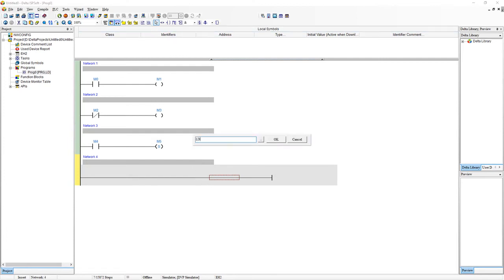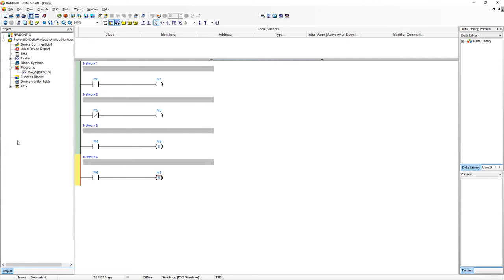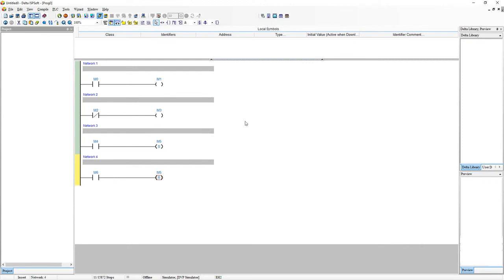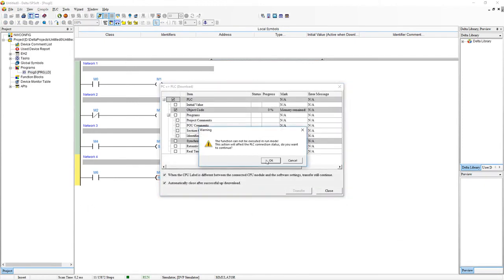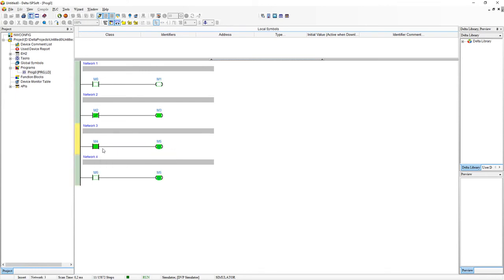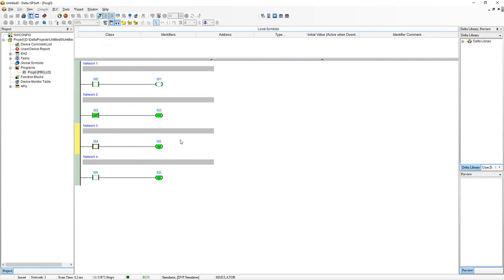So let's do LD M6. And we'll add RST as our function M5. So RST basically stands for reset. And I think it's quite obvious what this is going to do. But let's go into online mode and just demonstrate what it does. Alright great. So let's turn M4 on. So M5 is on. Turn it off. And M5 remains on. Let's turn M6 on. And you'll see that it resets M5 back to its original state.